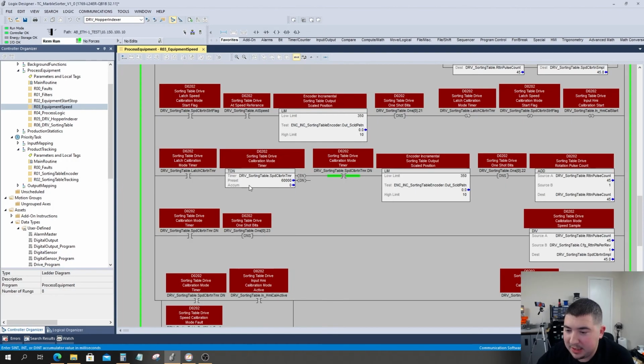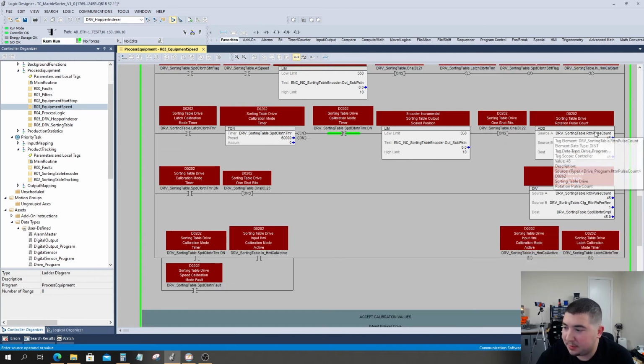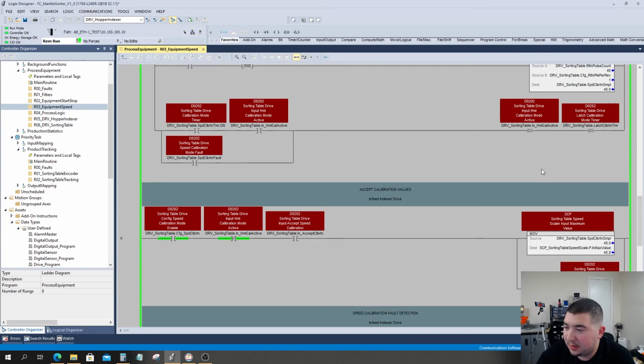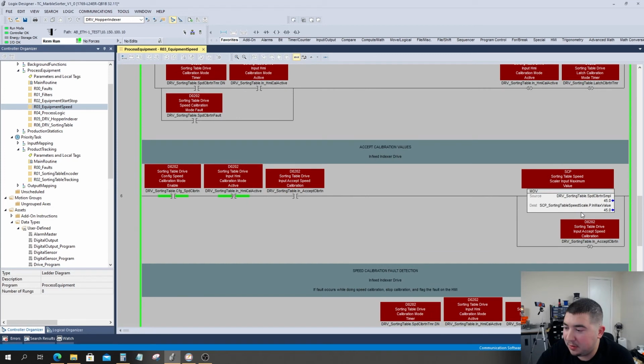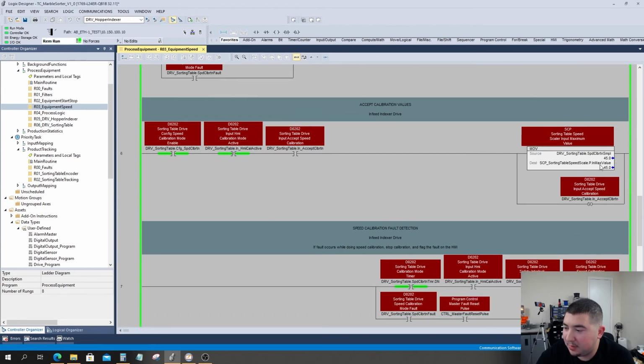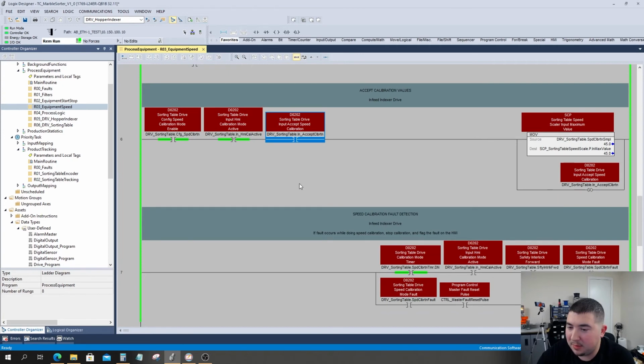Alright, so our speed test has just completed. So as we can see, our sample count is 45. So that means our speed sample speed was 45 RPM. And so that's our buffer value. And if you look here, we could accept this value, but because 45 is our maximum, we can assume that our relative speed is exactly the same as what we want it to be. So whatever we command is going to be exactly the same RPM.